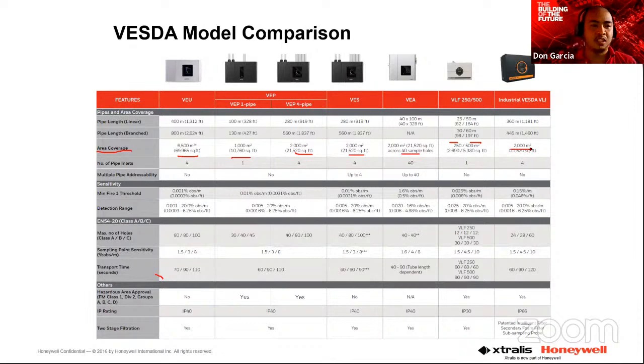So if there's an area we need to monitor with a detector, this is the first thing we check to know which aspirating system we will use. The rest, we design based on the standard, like the detector range, threshold of alarm, and maximum number of holes depending on the class of fire, like class A, class B, or class C.